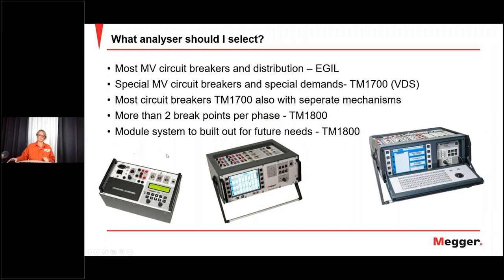it can be possible also with EGIL, but remember here you can only control one mechanism. You can only measure one mechanism. You can actually control the two, three, the common, not only the common one, but separate ones. But you can only measure one coil current here. And you have a limitation of only one analog channel. That's the limitation of EGIL.